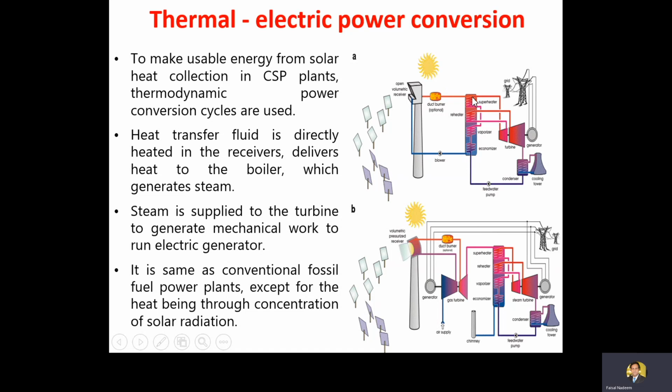So in the heat exchanger, this working fluid basically exchanges its heat with the water. And where is this water coming from? This water is coming from a nearby lake or something like that. Then it reaches here, and then it passes through this heat exchanger. The oil or the working fluid coming from the solar tower basically exchanges its heat in this exchanger. It loses its heat and gets cooled down, and the water, which is at normal temperature, gets that heat from the heat exchanger, gets heated up and converts that heat into steam.